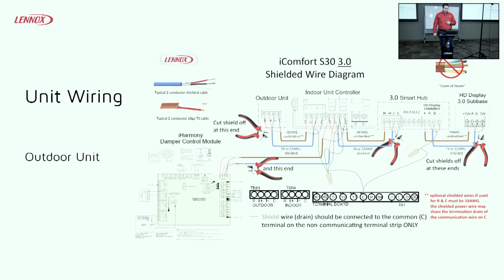So your outdoor unit is going to be pretty straightforward at that point. You have a couple of different options, because these can be used with non-communicating outdoor units. But in a communicating system, you just need your 4 wires going outside, or R, I plus, I minus, and common. Again, if we can do that in 2 runs, a 2 conductor, that's going to be the best thing we can do for future operation. If you end up installing on a heat pump, the pressure switch out there, remember, you'll need an additional 2 conductors outside for that.